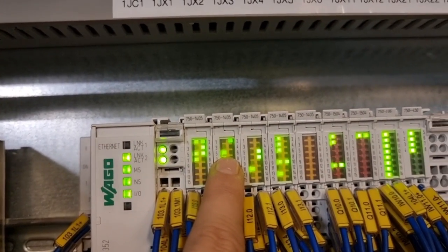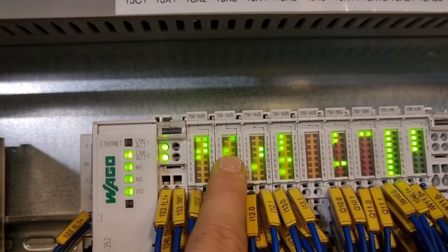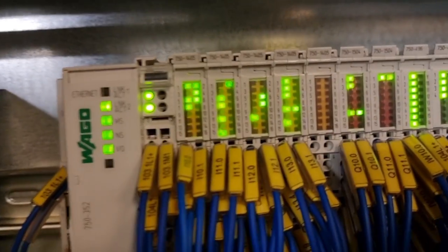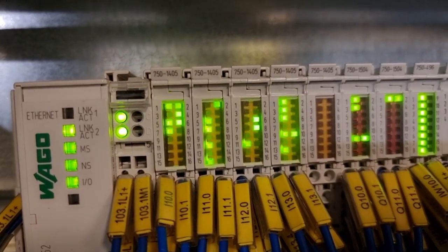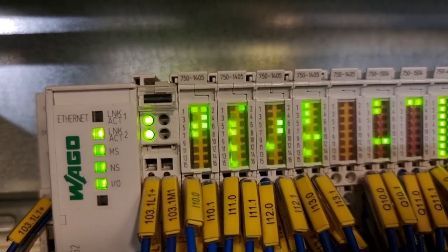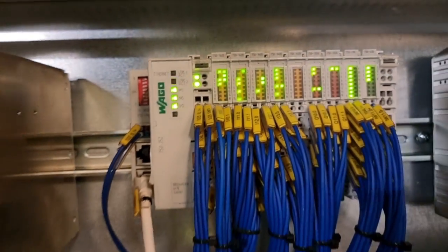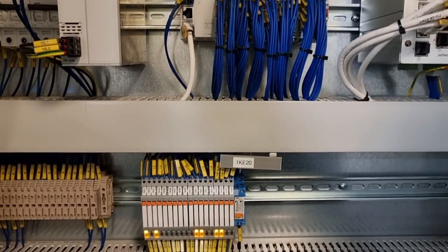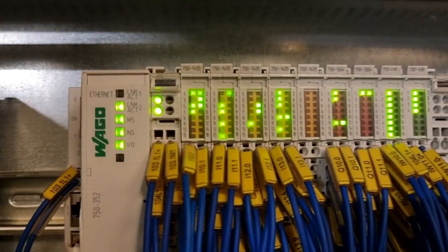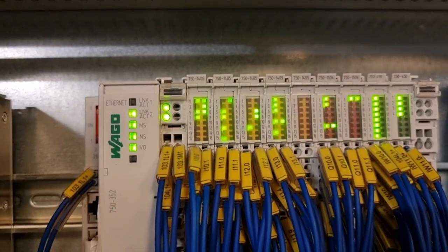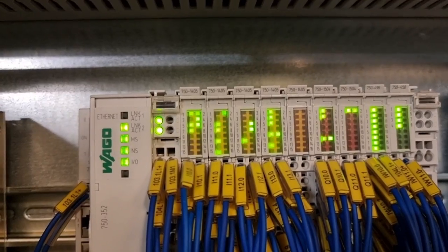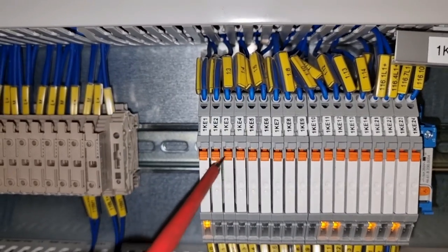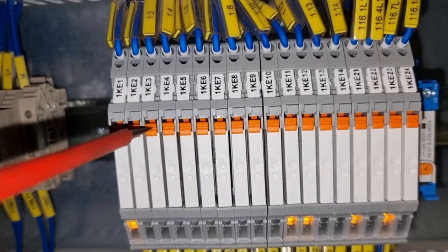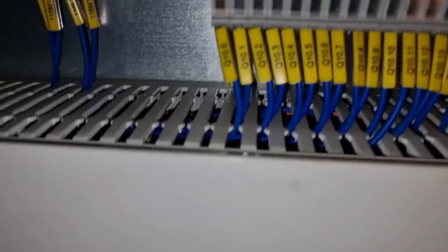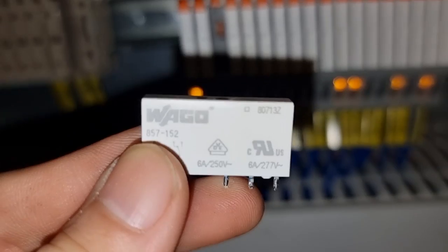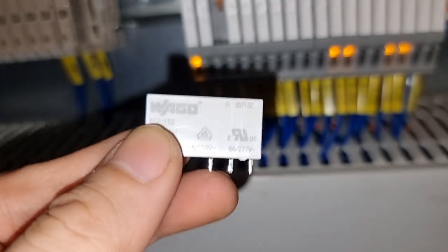And of course, since it's not giving 24 volts to our module, it will stay in closed position, which is number 5 LED on the 1JX3 module. So it means that the valve did not move at all. In this situation, we already know where the problem is coming from. So we need to replace that small relay and see what will happen next. To replace it, we just need to push this locking mechanism and it will pop out. So let's check if we have this spare and replace this defective one.